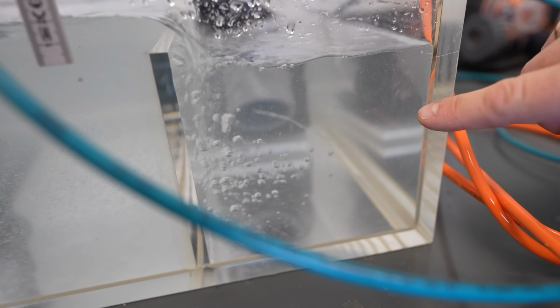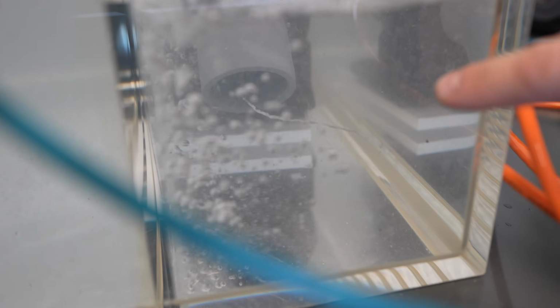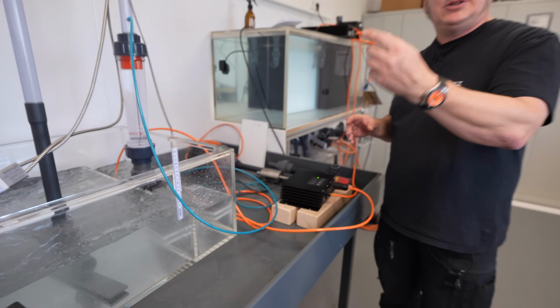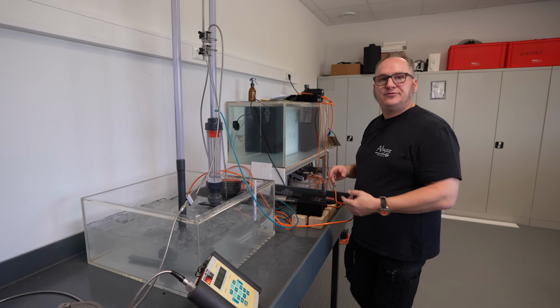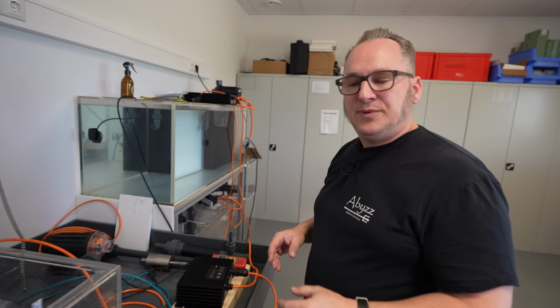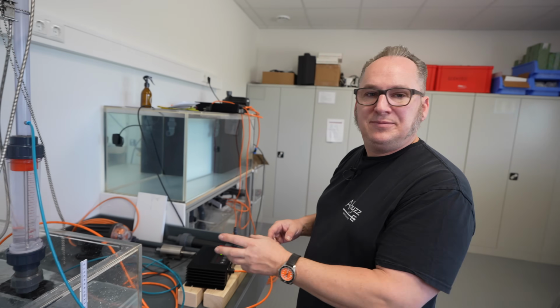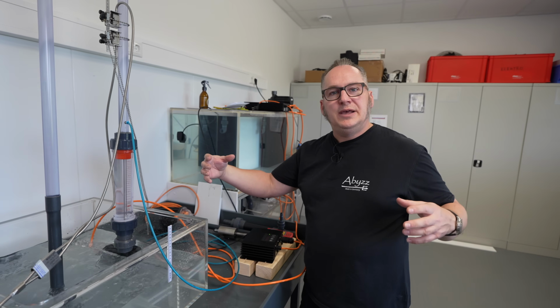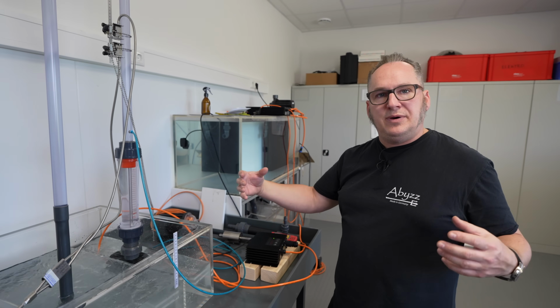What you can also see here on the intake very clearly is that if you have turbulences, this is by far not an ideal situation for a pump. So it's dragging in air. It's also drawing this little vortex here, which means that the water is actually circulating when it's entering that 45-degree elbow, and that's where you can see that this can't be very efficient. So if you have a longer run with no air getting into the pump, it will be much healthier. This can also cause a terrible TGP problem.